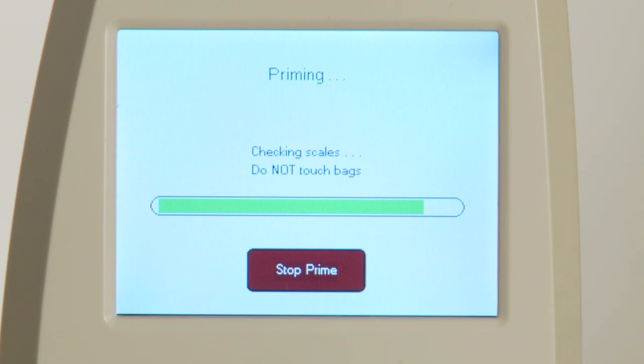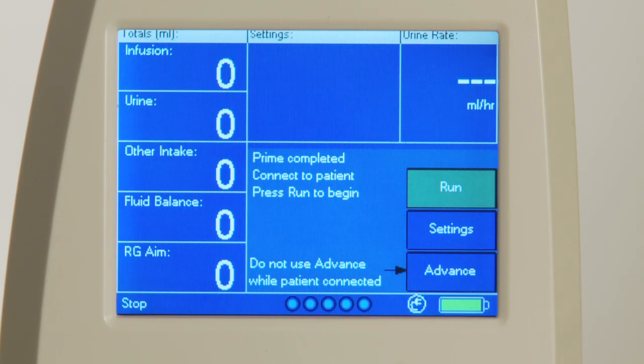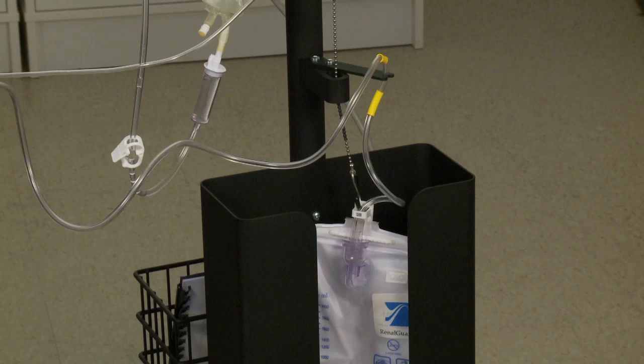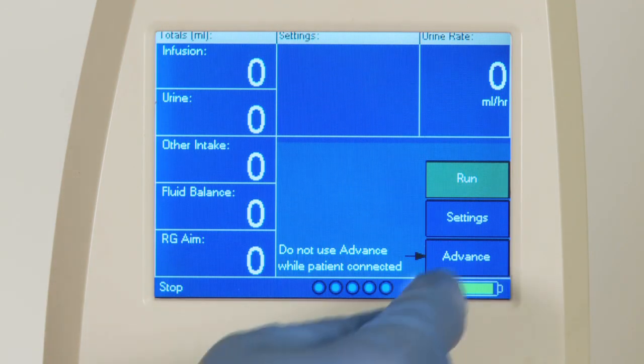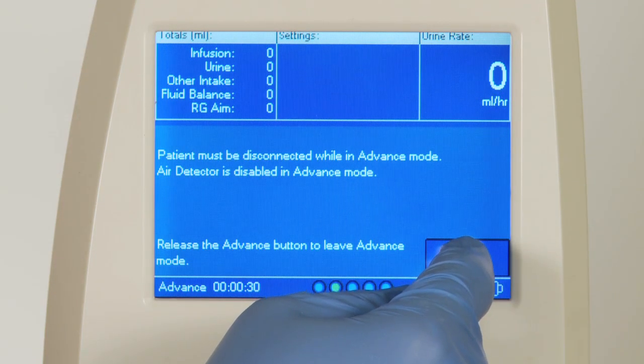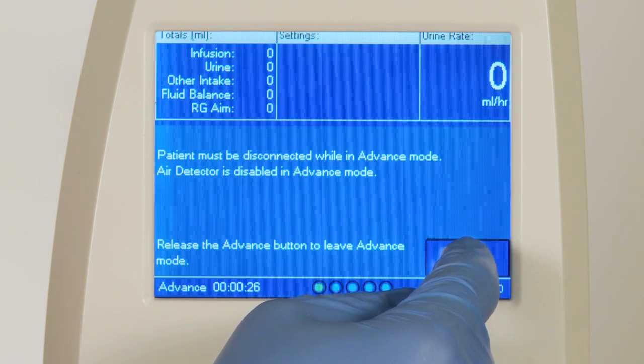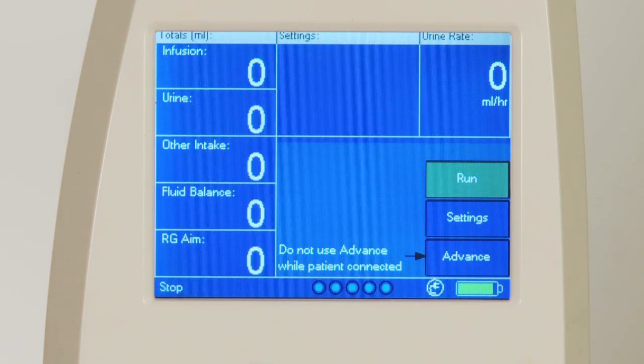Once prime passes and the pump stops, you will see this screen. Examine the infusion set to ensure no air is present and the set is not leaking. If air remains in the infusion set after prime, use the Advance button to remove it. Press and hold the Advance key to run the pump to purge air from the infusion set. Warning: air detection is disabled during Advance button operation. The Advance button must not be pressed while the infusion set is connected to the patient.